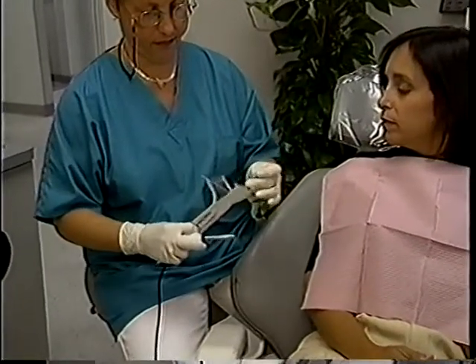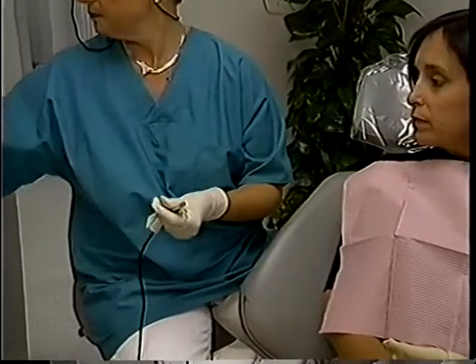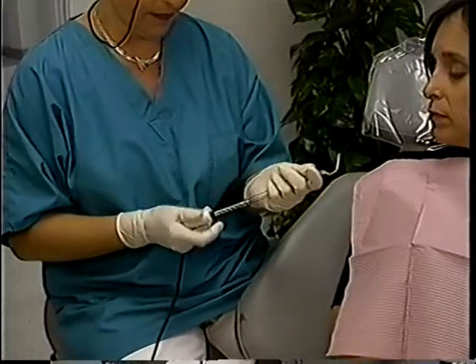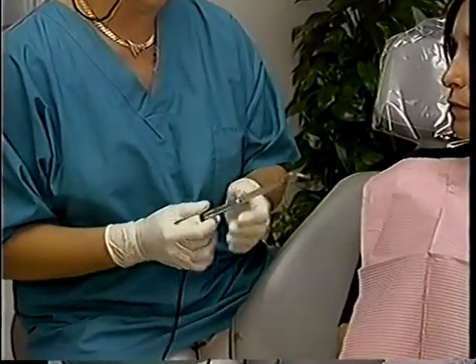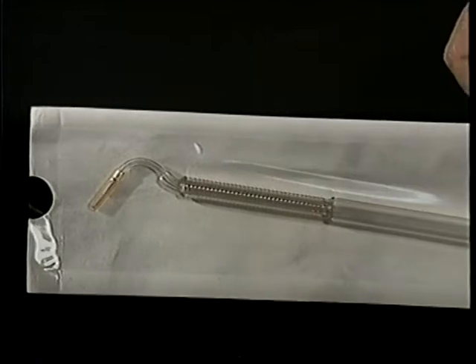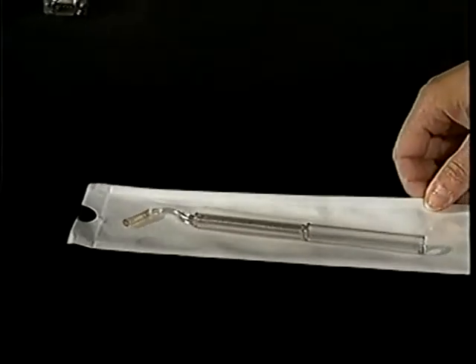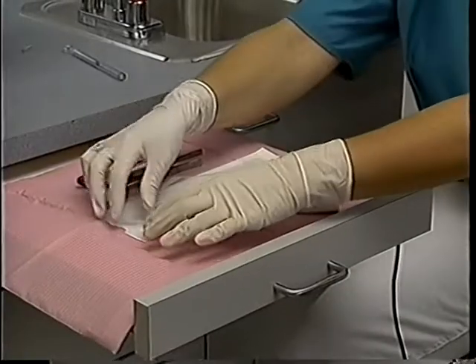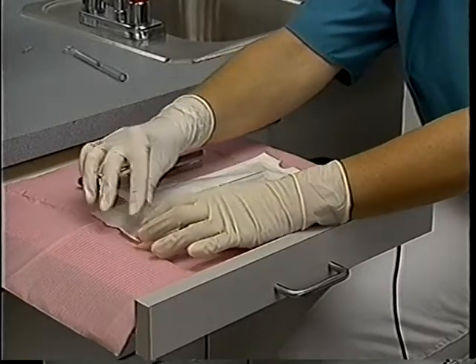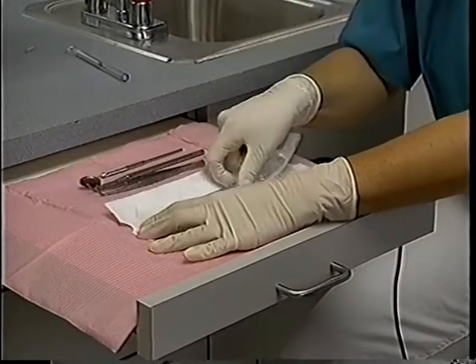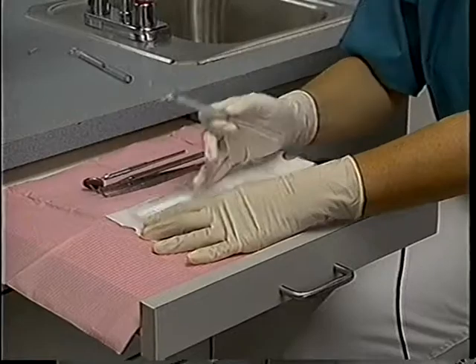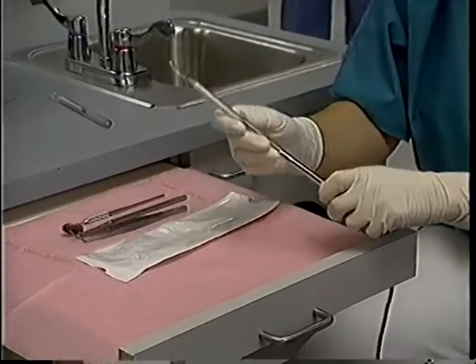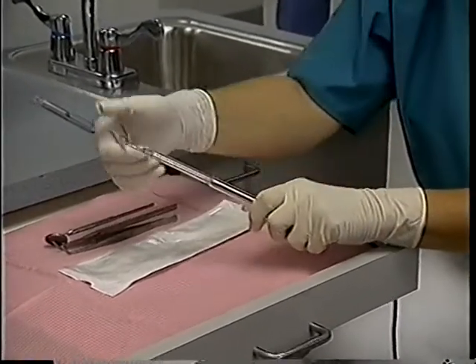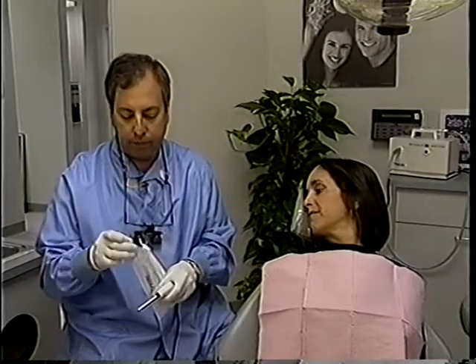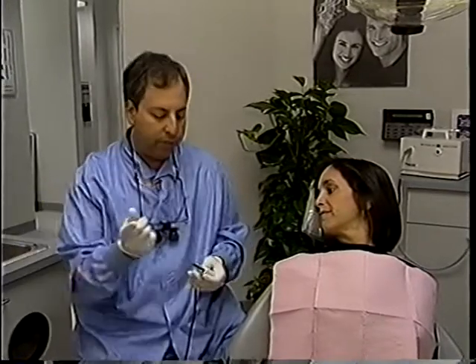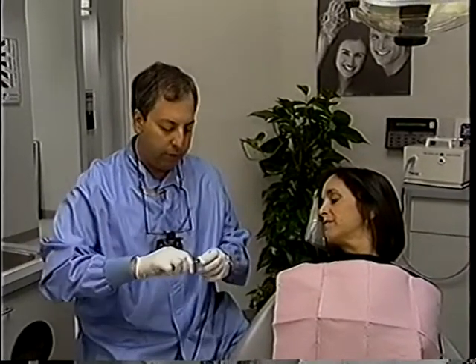Now that the Probe One is interfaced with your software, it's time to place one of the disposable tips on the encoder handpiece. Again, each tip is encased in a sterile package for infection control. Remove the tip from the package and place it over the shaft of the encoder handpiece. Push the tip into the handpiece until you hear an audible snap. If you don't hear this snap, the tip may not be properly engaged and the Probe One may not function properly.